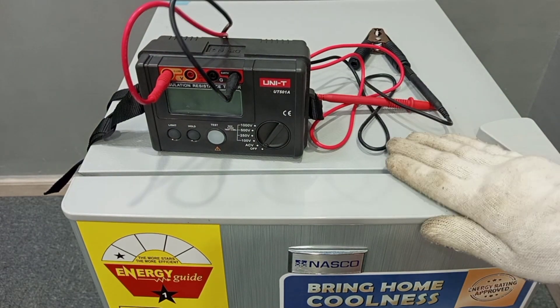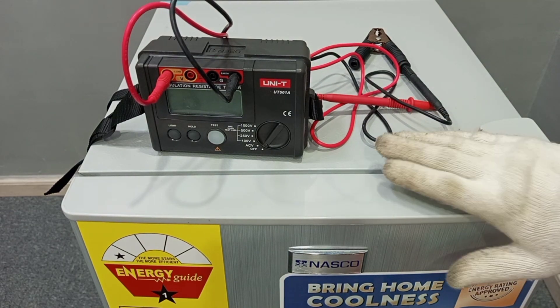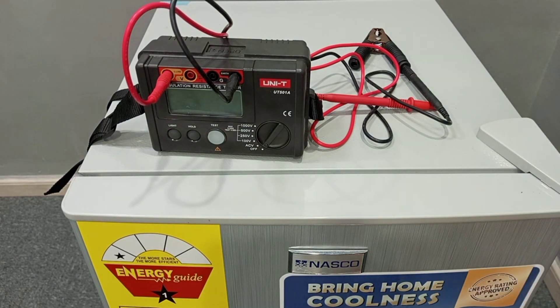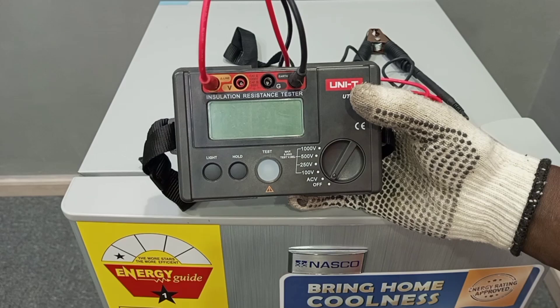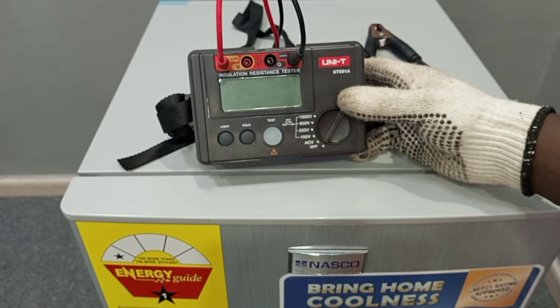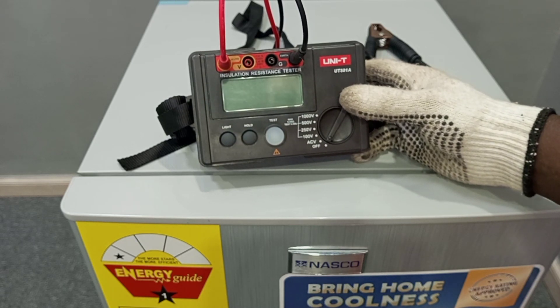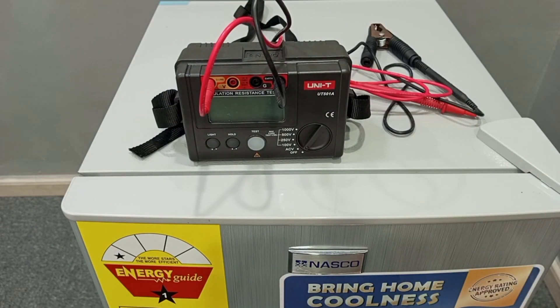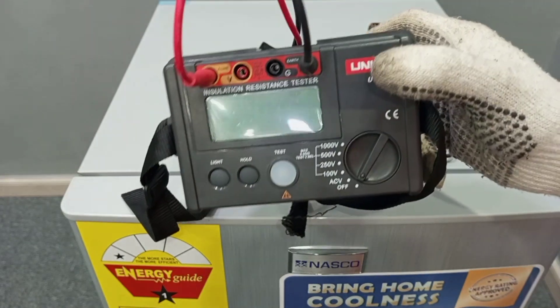The electrical appliance I'm going to use here is a fridge. We are going to use this fridge to learn how to do insulation resistance test on an electrical appliance or equipment. The instrument used for this type of test is known as the insulation resistance tester. People also call it a megger tester — megger tester is the same as insulation resistance tester. We have different types of them, but in this video I'm going to use this type to do the demonstration.